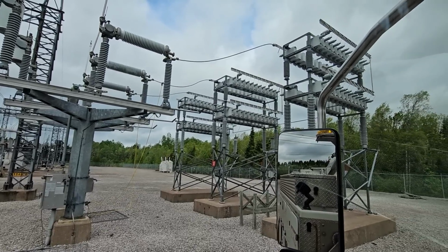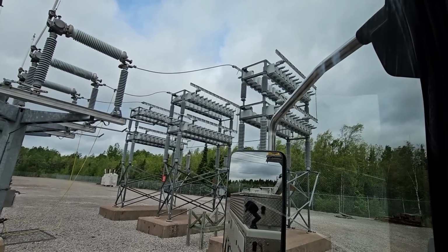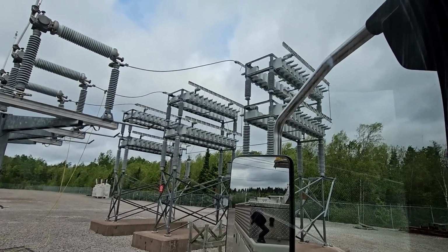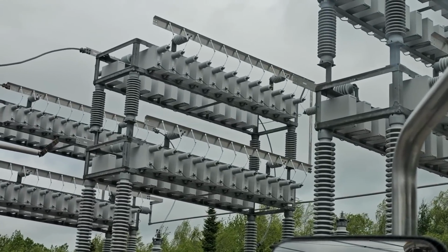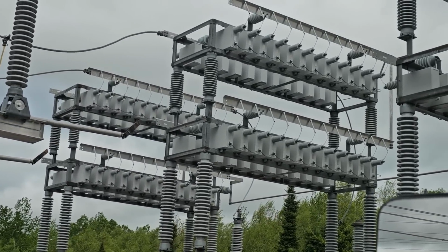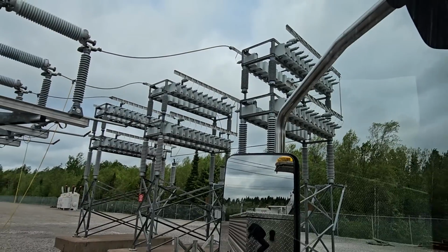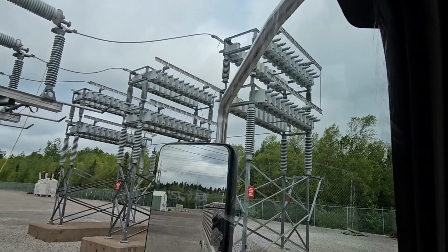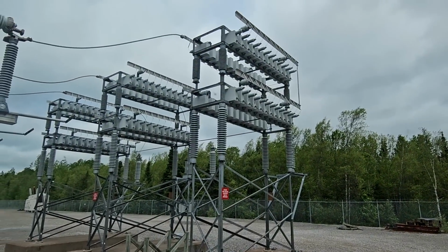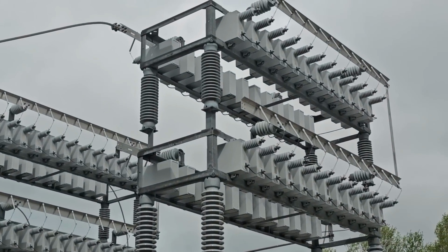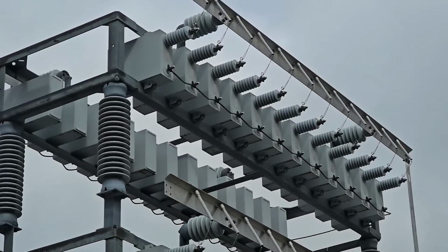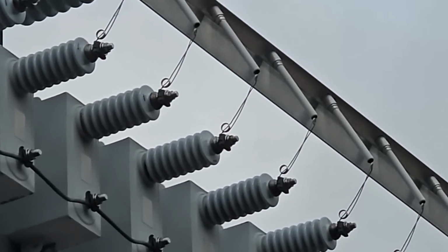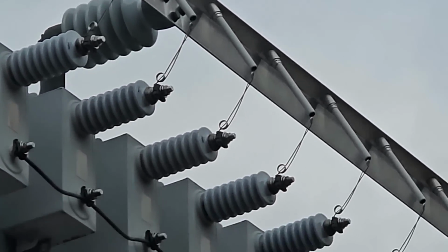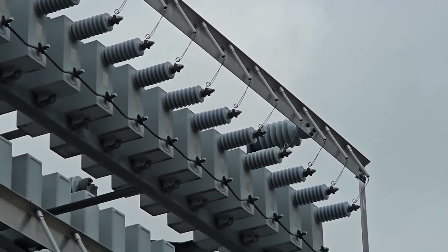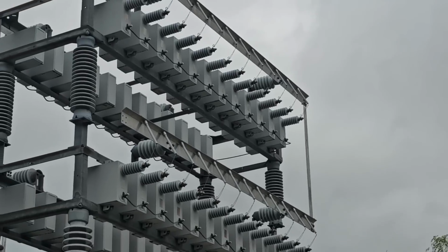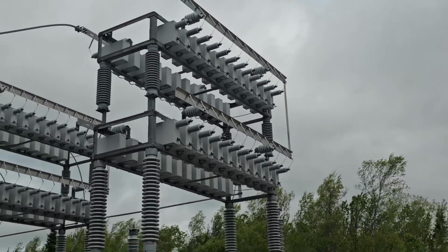So what we do to correct that, to make the system more efficient, is we have capacitor banks out in the field. Since we're at a terminal, this isn't just a capacitor bank, this is a massive one for us in my little old province. There's a ton of capacitors connected all in parallel there, and those tiny little wires, those are all fuses. Usually when I drive by, I make sure none of the fuses are popped. If there is, I'll report that. It's not something that's an emergency.